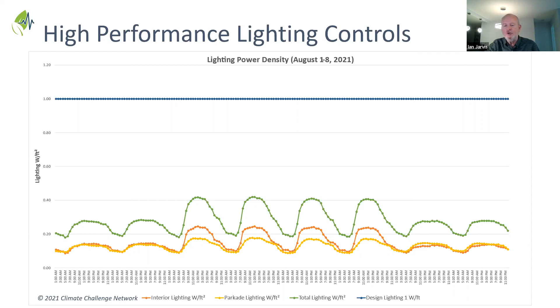With 1 watt per square foot of installed lighting, the actual operational lighting, including both the parkade and interior lighting, never went above 0.4 watts per square foot. This has been an exceptionally well-controlled lighting system, and when we run those numbers, we're operating at something like 25% of the actual load factor of the lighting over time.